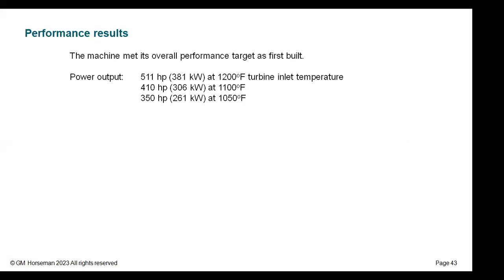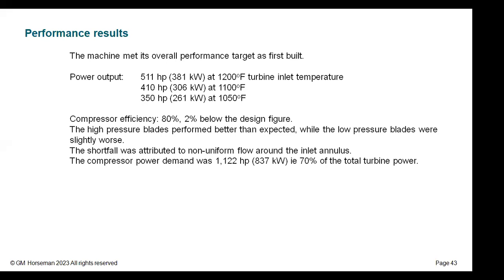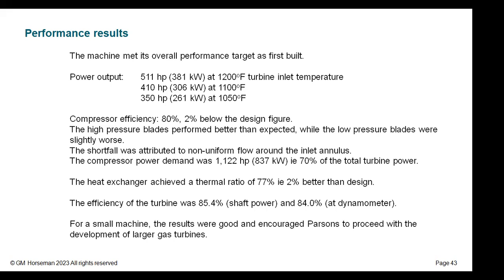Performance results. It immediately met its performance target, which was good news. So a 500 horsepower motor achieved 511 at 1200 Fahrenheit. Obviously, as the temperature was lowered, the power output reduced. Compressor efficiency was 2% below performance. This is attributed to non-uniform fluid inlet, something that was addressed in later machines. Heat exchanger achieved 77% heat recovery, 2% better than target. Oh, and the turbine was 85.4% based on shaft power, 84% measured at the dynamometer.